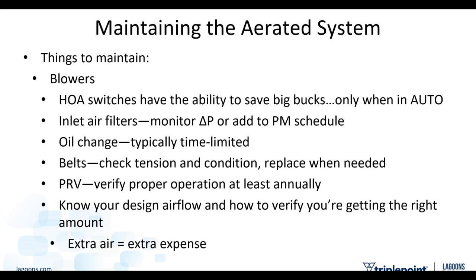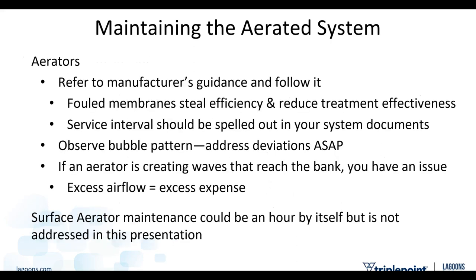Another recommendation here is to know your design airflow and how to verify that you're getting the right amount. Because quite frankly, extra air is just extra expense. You're just spending money that you don't need to spend. Those aerators, I recommend that you refer to the manufacturer's guidance and follow it. Fouled membranes will steal efficiency, they'll reduce treatment effectiveness, and they'll create problems with permit compliance. Keep an eye on your membranes, keep them clean. Service interval should be spelled out in your system documents.